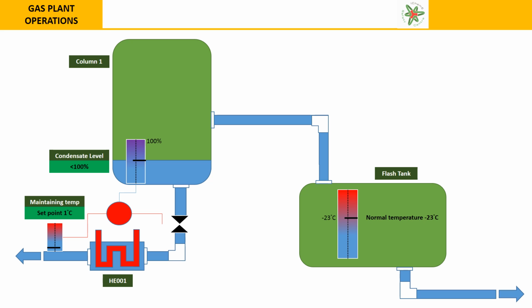The consequence that this has on column 1, it raises the condensate level in column 1 so that it rises above the 100% level. This cools down column 1, as we mentioned, from its normal minus 10 degrees to a new minus 20 to minus 25 degrees. When the level goes above 100%, product flows out the overflow line into the flash tank where it flashes and drops the temperature there from a normal minus 23 degrees to a new minus 33 degrees.